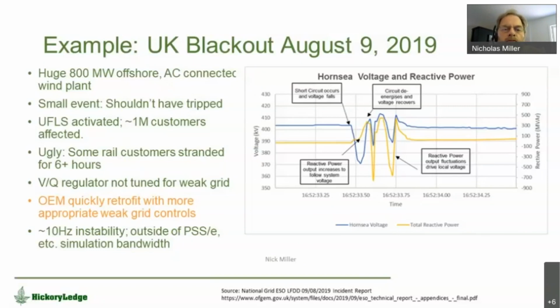They had a small event, and the plant misbehaved. It did not understand that the event had dropped the system's strength, driving it in the direction of being weaker. And what you see here are traces, oscillations, as it flogged for a couple of cycles of this instability and then tripped.